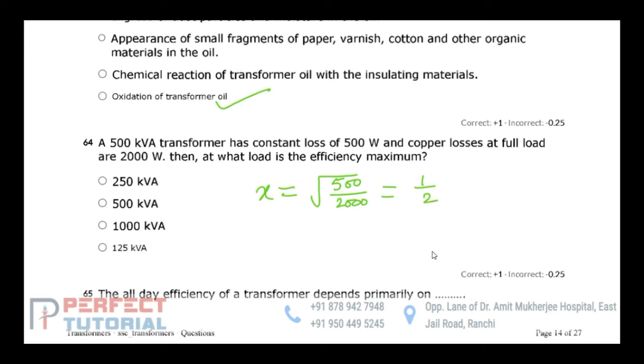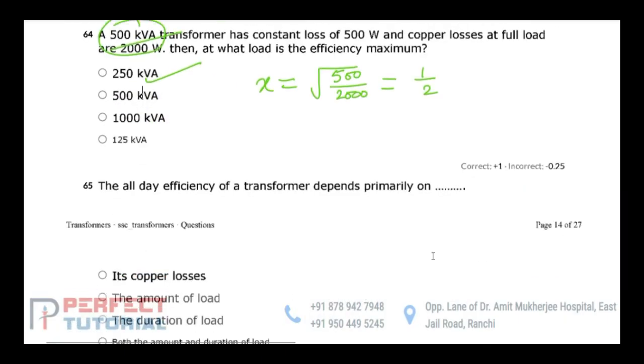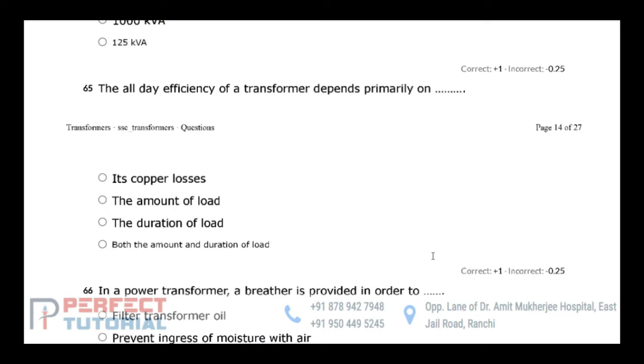Now what would be the load kVA at maximum efficiency? Load kVA at maximum efficiency is equal to the fraction of loading at which maximum efficiency occurs multiplied by the full load kVA. So 500 kVA multiplied by 1 by 2 would be the load kVA at maximum efficiency, that is equal to 250 kVA. Next, the all day efficiency of a transformer depends on both the amount and duration of load, or it depends on the load cycle as well as the amount of load.